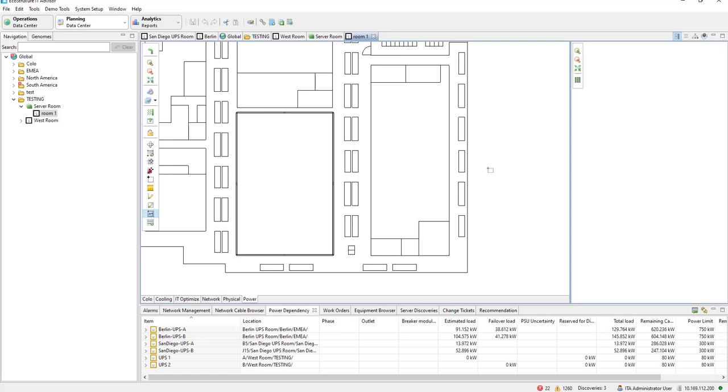The third, or the fourth point, sorry, that you mentioned is your UPSs and PDUs that are upstream. They need to be adjusted. Tomorrow is our last session of the POC. We should be able to look into that and try to adjust the configuration, or the values on those devices, so it matches the actual devices that you have in your data center, so you can actually see the power reading throughout the power path in the system.